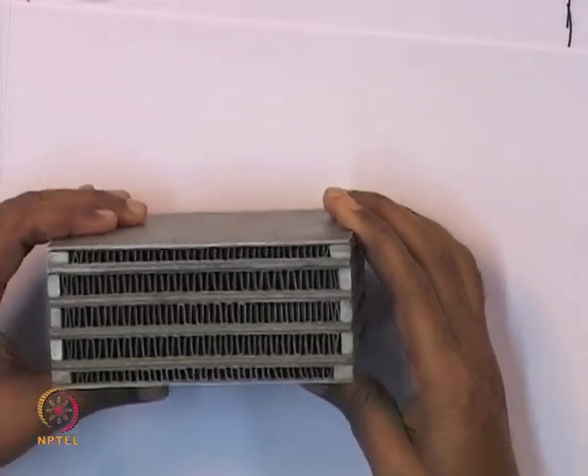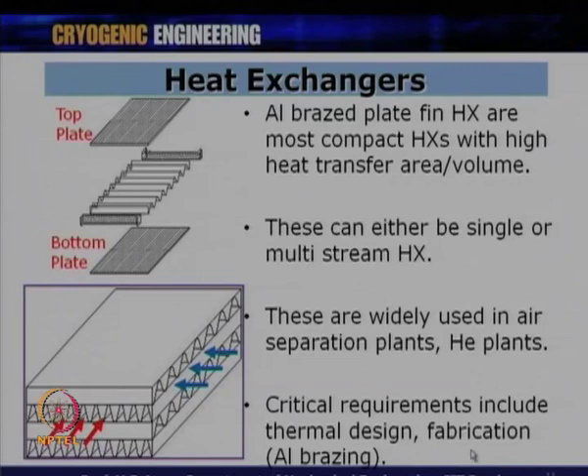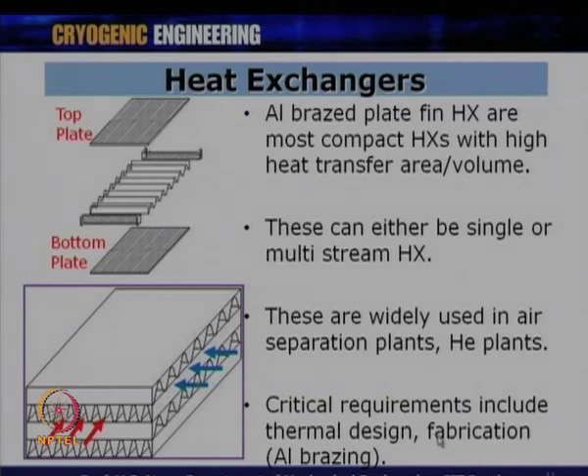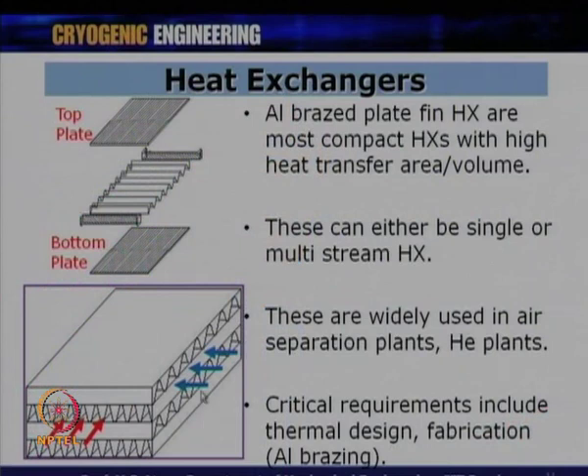The critical requirement for aluminum brazed plate-fin heat exchangers is the thermal design and fabrication, because aluminum brazing is not a simple process. Aluminum oxidizes immediately, so brazing requires extensive pre- and post-processing done in a vacuum or controlled environment. Thermal design is important depending on fins, fin efficiency, and types of fins. This is a very important device and is commonly used for all high-flow liquefaction systems.